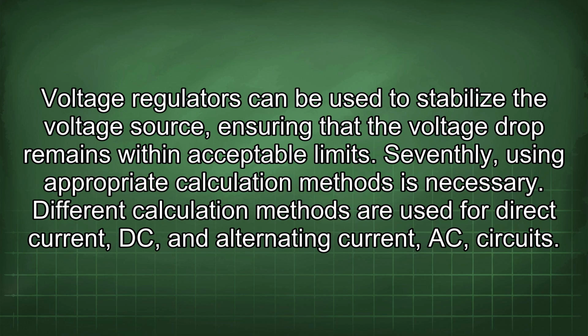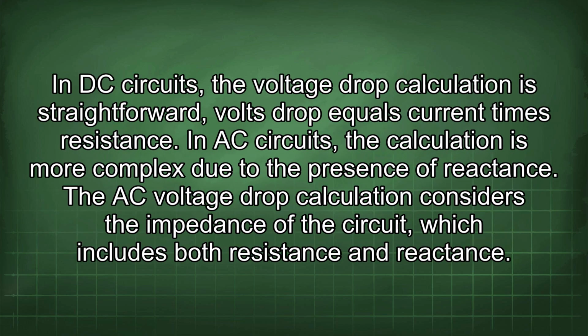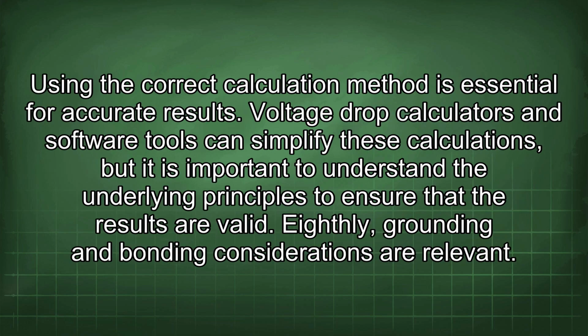Seventhly, using appropriate calculation methods is necessary. Different calculation methods are used for direct current (DC) and alternating current (AC) circuits. In DC circuits, the voltage drop calculation is straightforward: volts drop equals current times resistance. In AC circuits, the calculation is more complex due to the presence of reactance. The AC voltage drop calculation considers the impedance of the circuit, which includes both resistance and reactance. Using the correct calculation method is essential for accurate results.